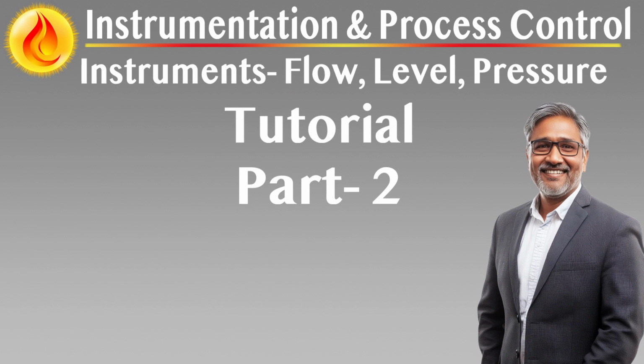Differential pressure instruments must be able to withstand full static pressure in both directions, accounting for possible misconnection, venting imbalances, or maintenance error. Instruments exposed to vacuum must be specified with absolute pressure tolerance and materials rated for subatmospheric service. For temperature extremes, e.g. cryogenic or high-temp reactors, process limits must include startup, shutdown, and upset conditions, not just steady-state operation. Specification documents and requisitions must clearly define upper and lower mechanical limits, not just the calibrated operating range, to prevent mismatch between installed conditions and vendor assumptions.